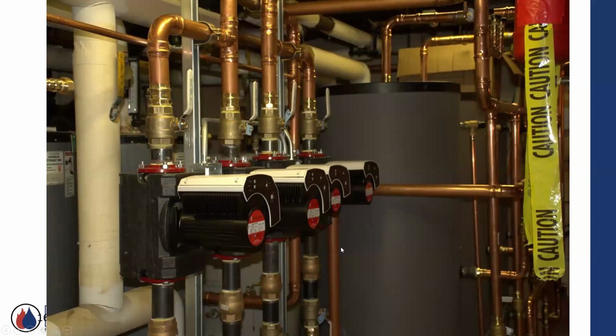So there's a quick example out in the field where I might have a couple of pumps going out to 24, 36 apartments upstairs. Right beside it, I have 2 pumps, one standby, one in operation. And maybe it's feeding the domestic hot water production down in the basement. I'll say, hey, I can put a pump in and dial in exactly what the manufacturer of these domestic hot water tanks says I need to get my maximum performance. And I'll do that. So right here, I have basically the same pumps, but I'm using them in different modes by simply selecting, as I turn the pump on, what my mode is. I want to do proportional pressure for all the zone valves upstairs. I want to do a constant speed for these domestic tanks right here.